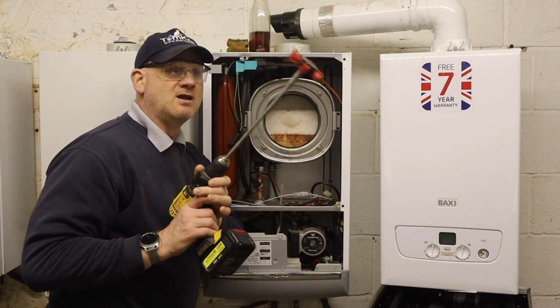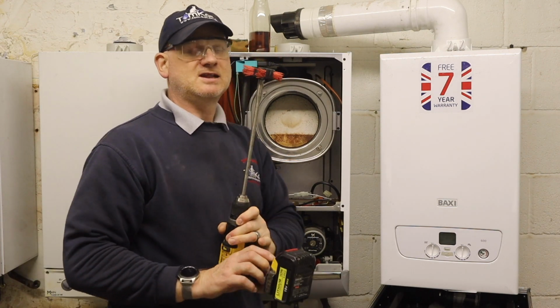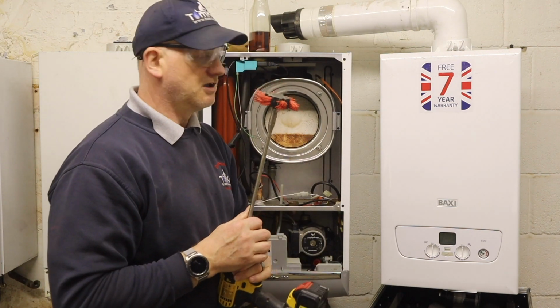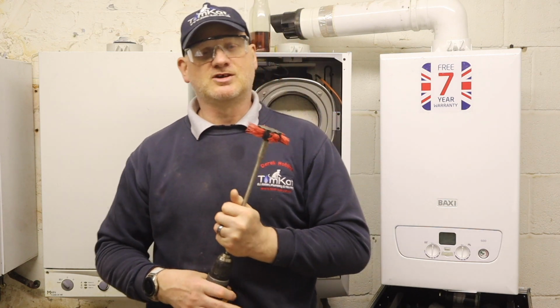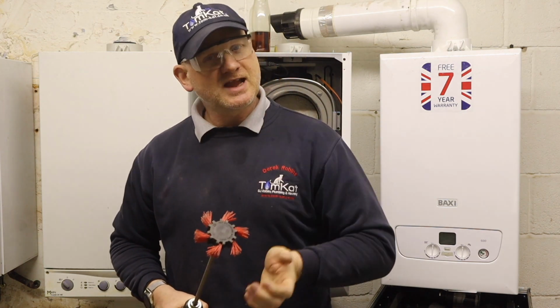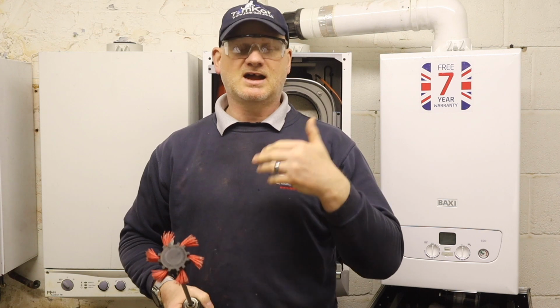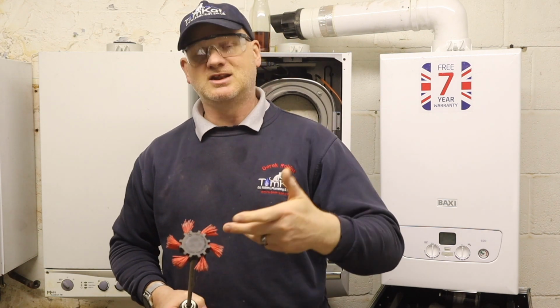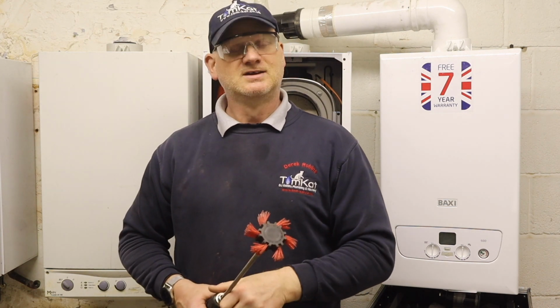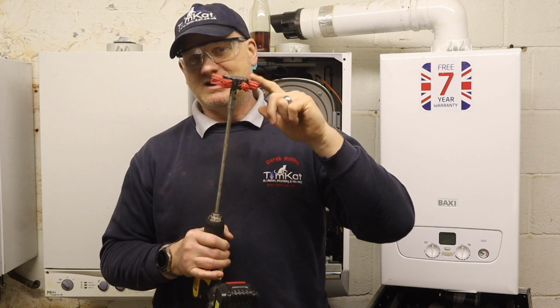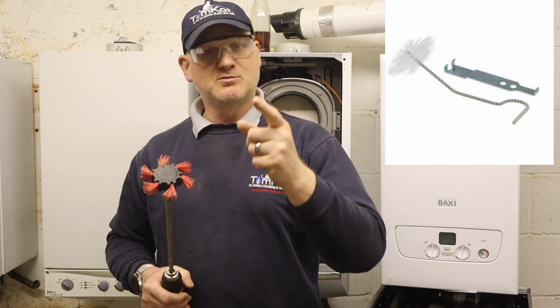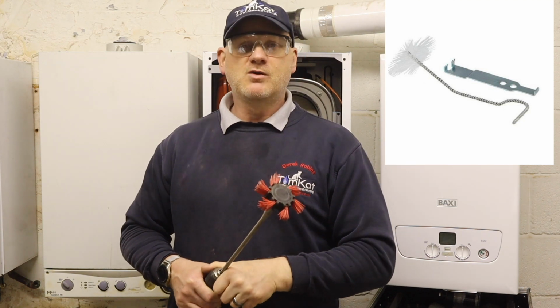So that's using this little cleaning brush and vinegar to clean a heat exchanger. This is only for stainless steel heat exchangers, guys. Aluminium heat exchangers you can clean to the manufacturer's instructions - you won't be able to get this brush in anyway, but some manufacturers do make cleaning brushes for their own heat exchanger.